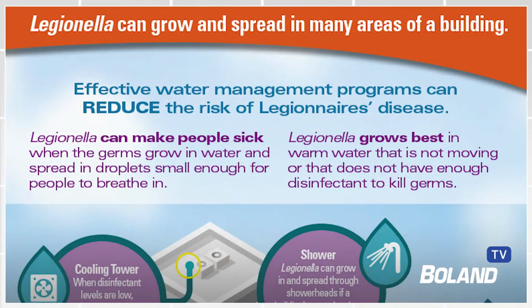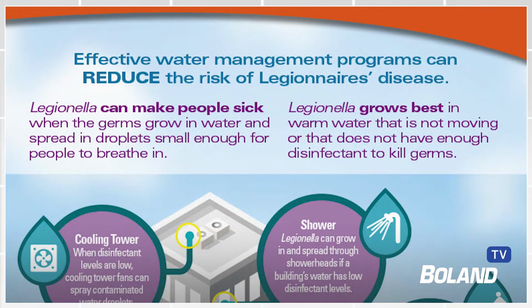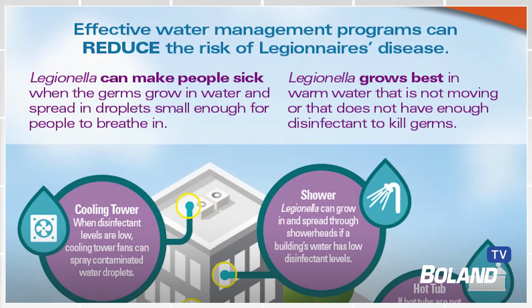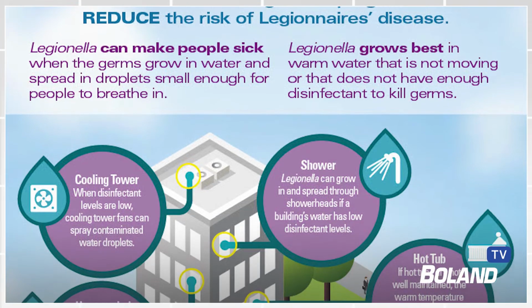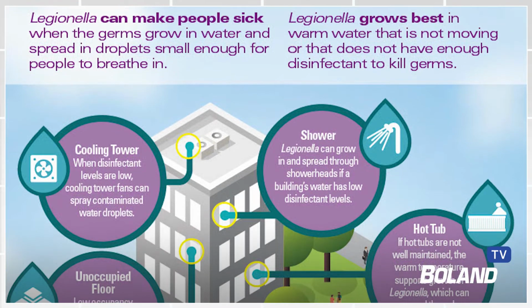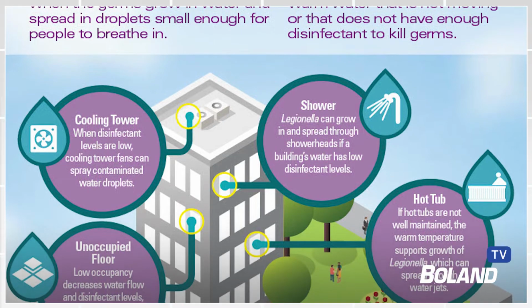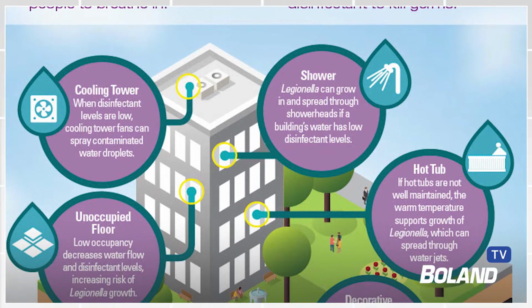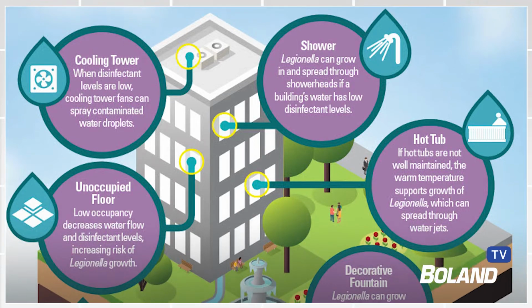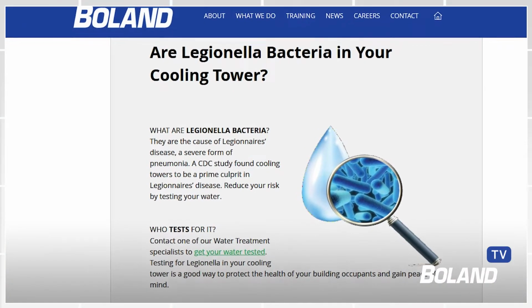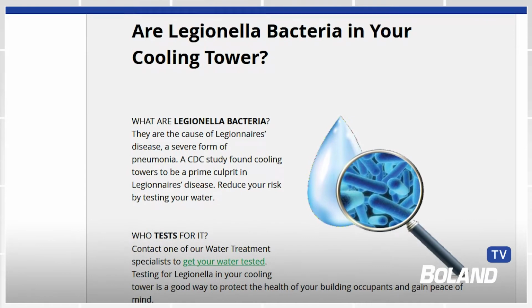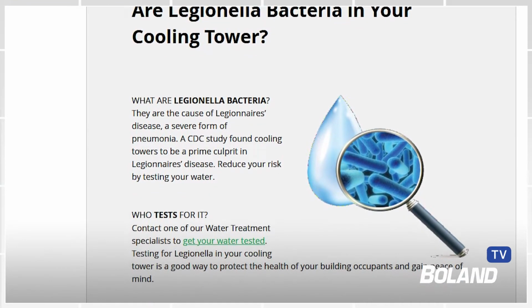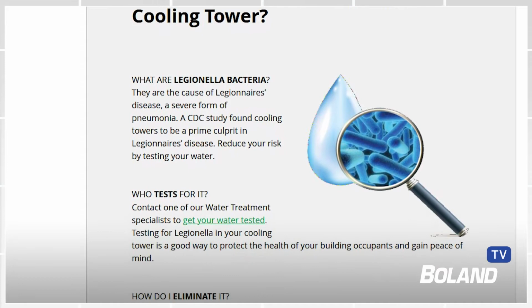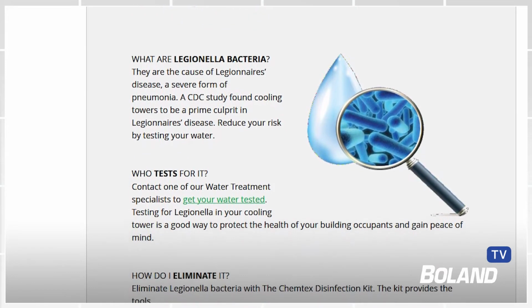Dirty towers really add up, and when you have a dirty tower into the summertime, it really uses up all of the biocide that a water treater might feed. So for instance, if we're feeding chlorine to kill bacteria, instead of killing the bacteria, it'll get used up on other organic debris, such as sand, silt, all that stuff that gets scrubbed in from the outside by the cooling tower. So keeping cooling towers clean is vital to prevent and to keep bacteria levels low.